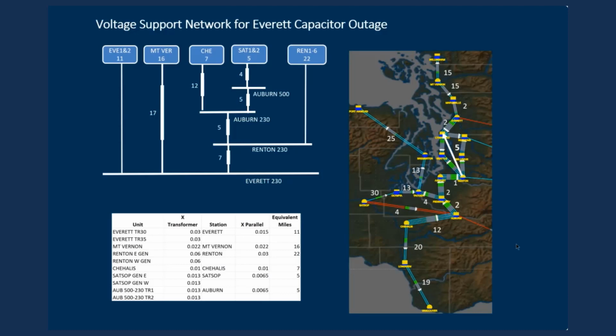So we start out and we assign a distance within each of our generators to represent the generator step-up transformers. So for Everett, it is 11 miles. For Mount Vernon, it is 16 miles. For Chehalis, it's 7 miles. For Satsop, for both units 1 and 2, it's 5 miles. And for Renton, for all 6 units, which are fed through 2 parallel transformers, it's 22 miles.